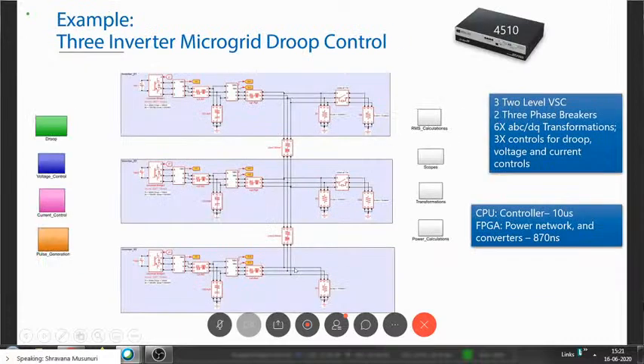So I have a 3-inverter microgrid droop control where I have 2-level voltage source converters, 2 breakers, 6 times ABC to DQ transformation happens, and 3 times the droop controls of voltage and current happen. I wanted this entire controller to run in 10 microseconds and the FPGA to run at 800 nanoseconds. So I wanted to see if we could do it in this or not.